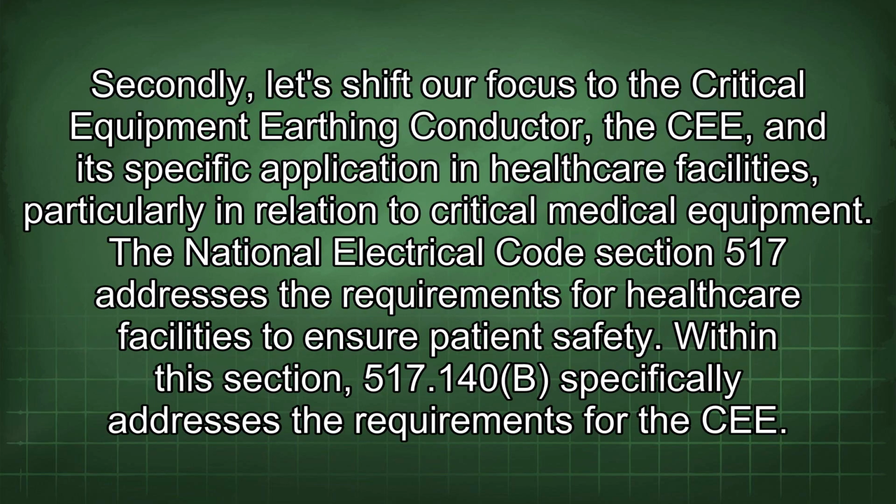Secondly, let's shift our focus to the critical equipment earthing conductor, the CEE, and its specific application in healthcare facilities, particularly in relation to critical medical equipment. The National Electrical Code Section 517 addresses the requirements for healthcare facilities to ensure patient safety. Within this section, 517.140b specifically addresses the requirements for the CEE.